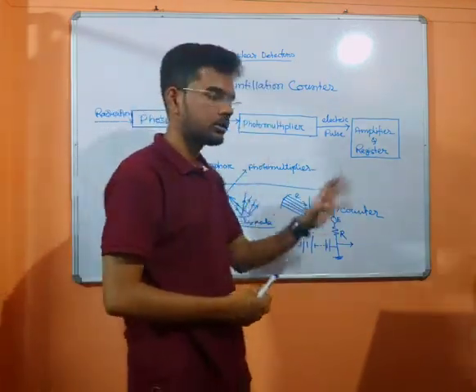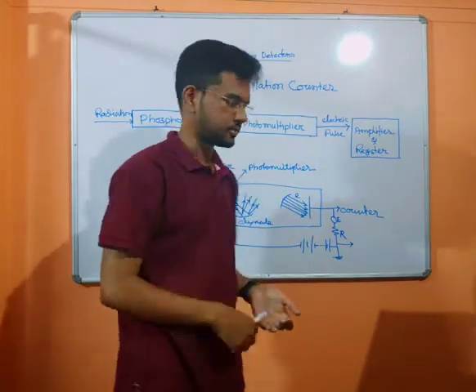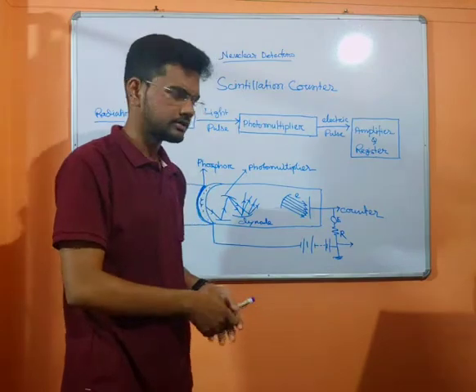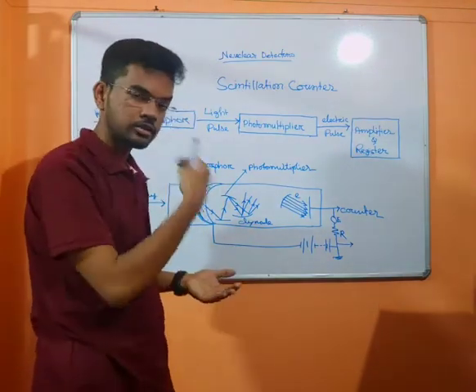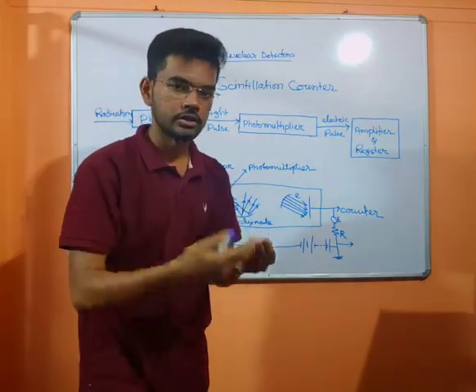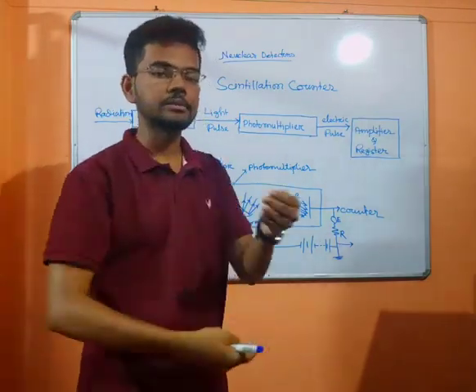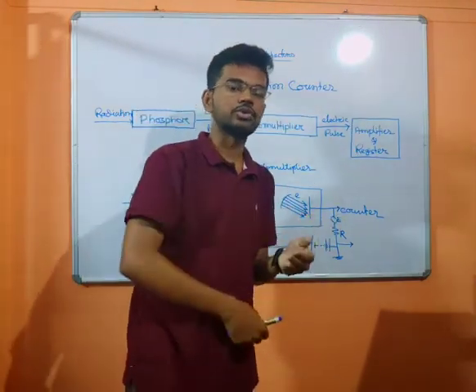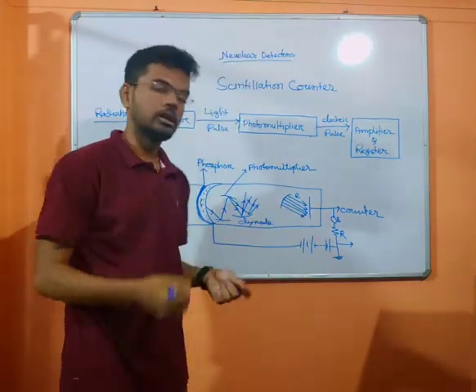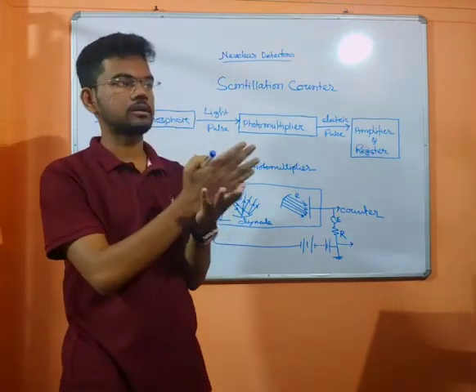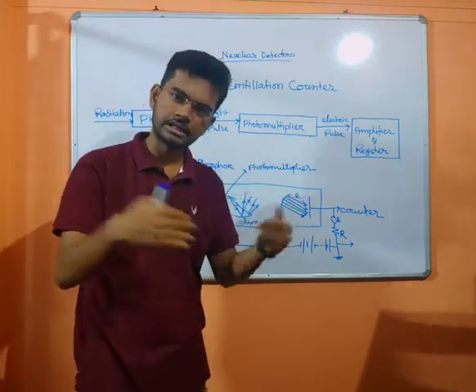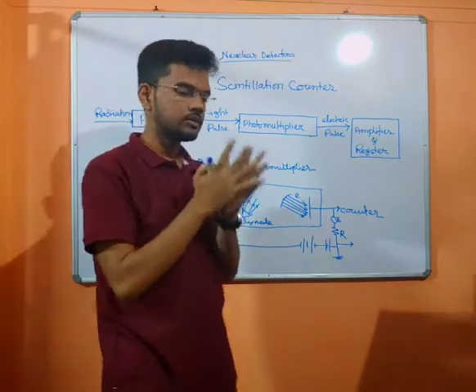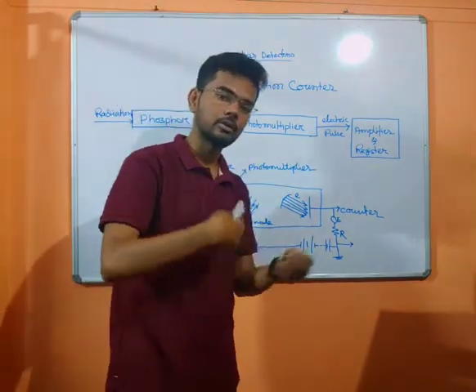With the plate connected, we can count and register the nuclear particle information. The X-ray incident on phosphor produces a light impulse — called scintillation. Scintillation hits the cathode, electrons are produced, and the light impulse is converted to an electric impulse by the photomultiplier. The electric impulse is then brought to the dynode.